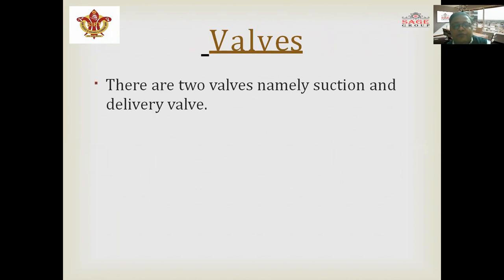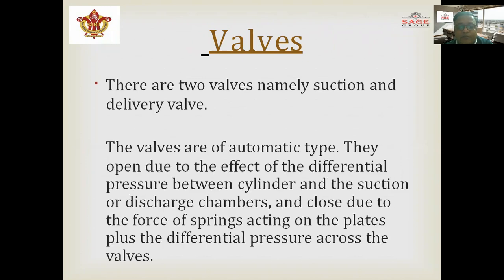There are two types of valves used in the engine cylinder: one for incoming air and one for discharging compressed air. The valves are automatically actuated by the effect of differential pressure between the cylinder and the suction or discharge chamber, and close due to the force of a spring acting on the plates plus the differential pressure across the valve.